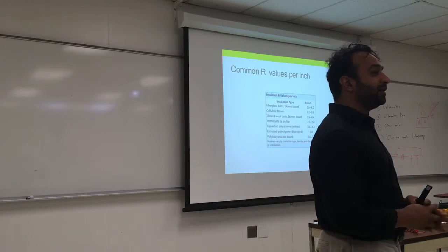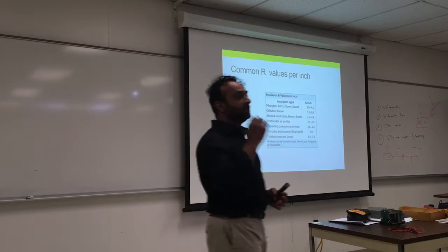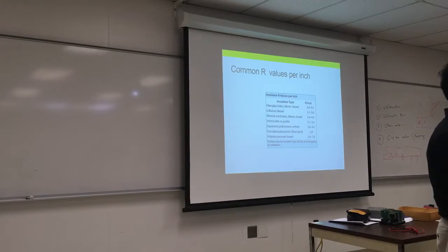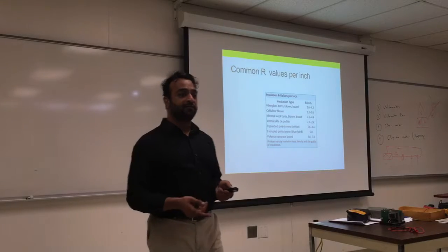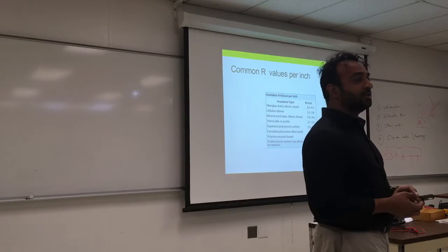Okay, so this is week 5, and we're doing part 2 of insulation. We talked about all different kinds of insulation, the relationship between density and R value. And what is R value related to? The U value. Well, the U value depends on the R value. The R value depends on the thermal conductivity of the material and the thickness. So you might buy some material and it has a K value and it has thickness, and you find the R value using those.